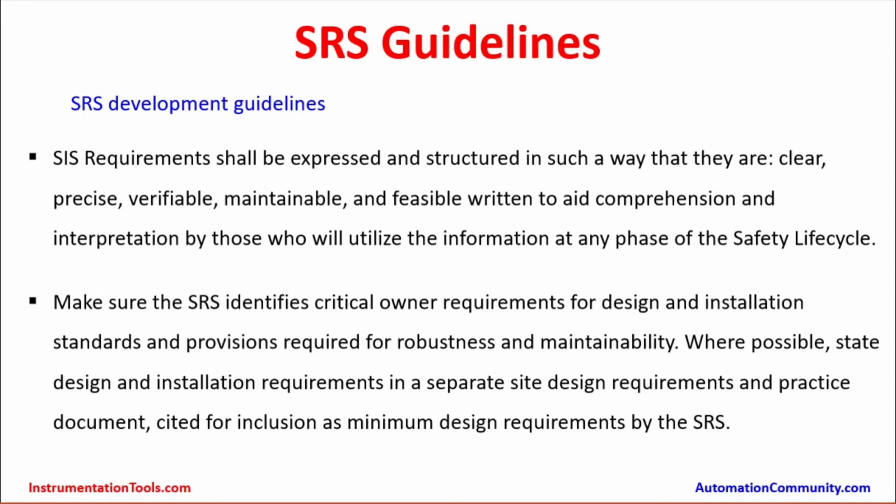So that has to be very clear and precise, so that the users and engineers who are going to do regular maintenance understand and apply it during the entire plant life cycle. So make sure that the SRS identifies the critical owner requirements for design and installation standards and provisions required for robustness and maintainability. Where possible, state design and installation requirements in a separate site design requirements and practice document, cited for inclusion as minimum design requirements by the SRS.